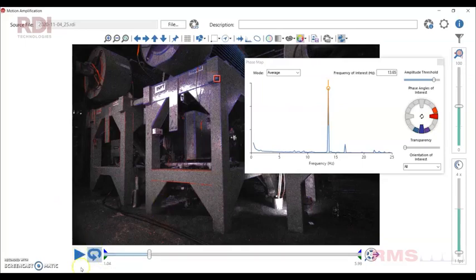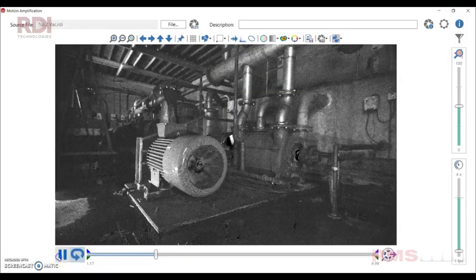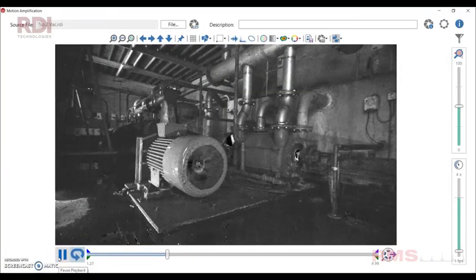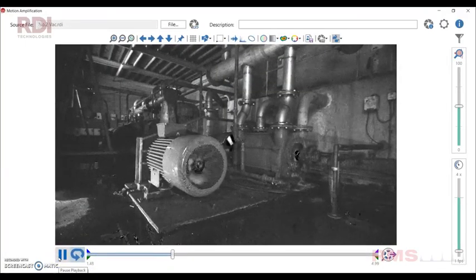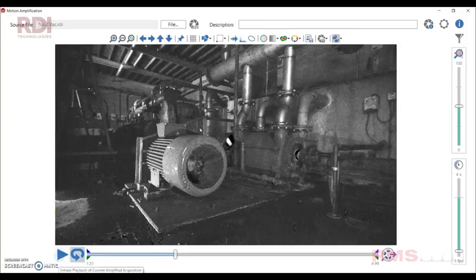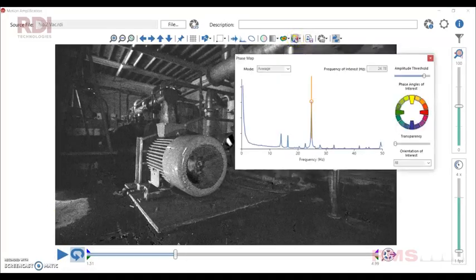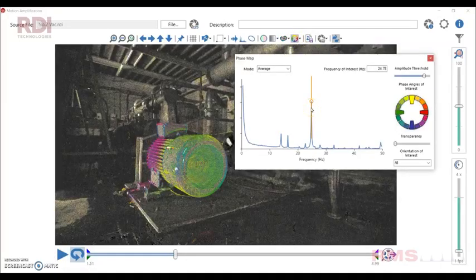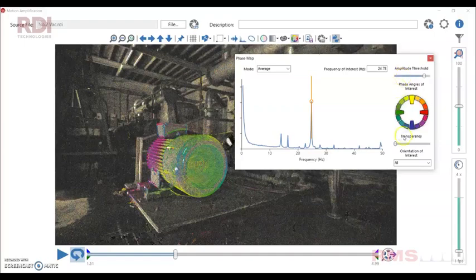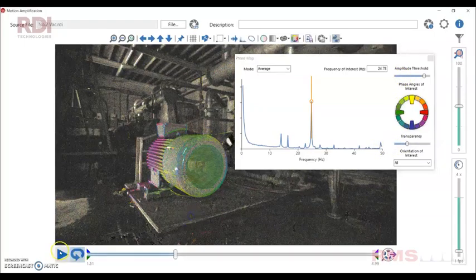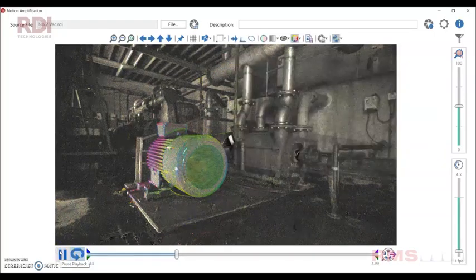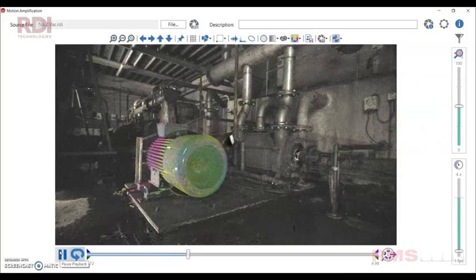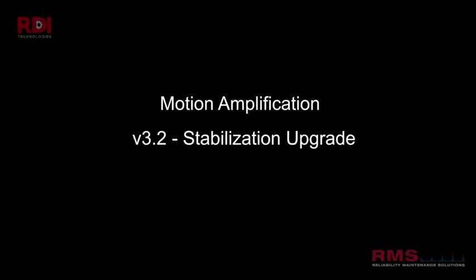Got another example here. This is a motor rocking due to a base problem. And you can see when we overlay that. Real contrasting colours there. 180 degrees. Drive end to non-drive end rocking there. And if you add a bit of transparency you can even show a bit of the motion in the video.